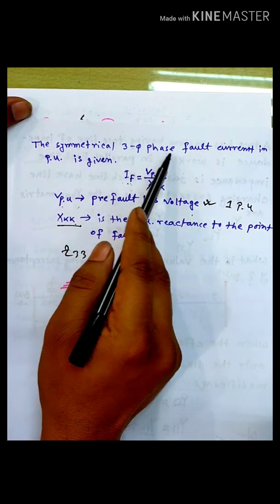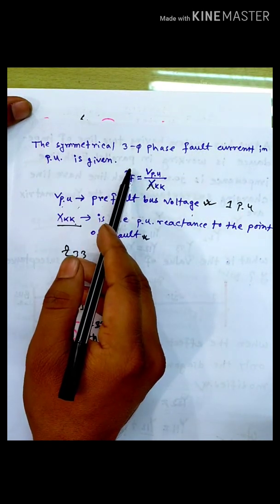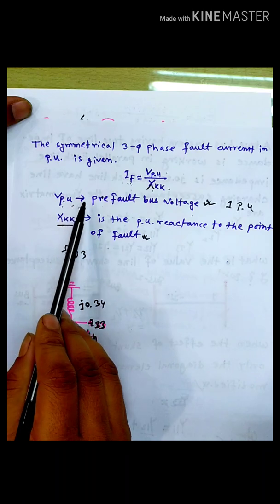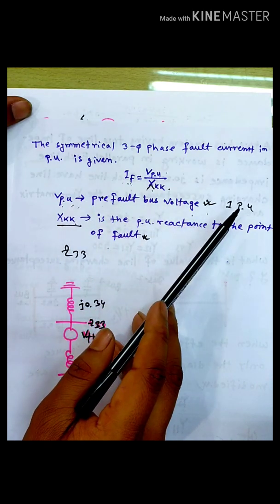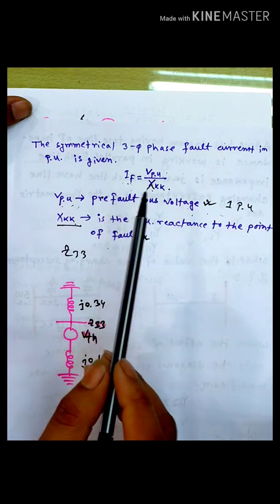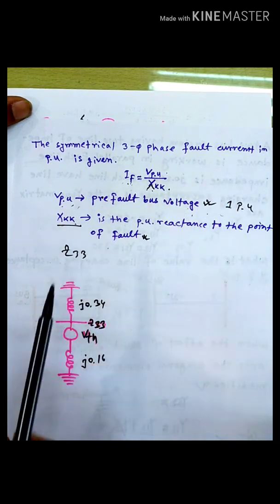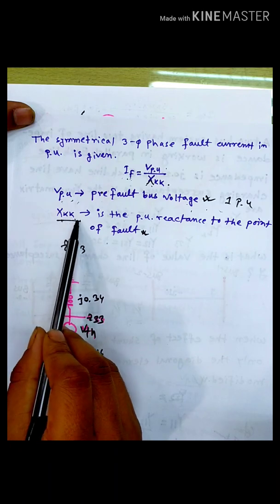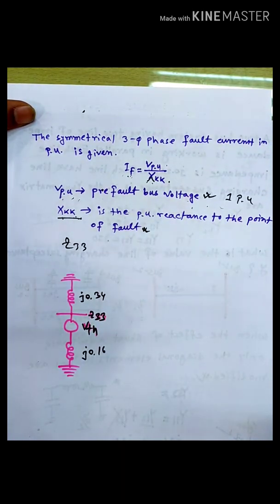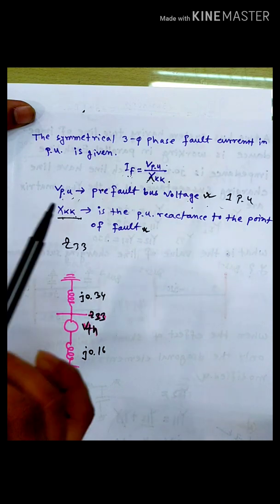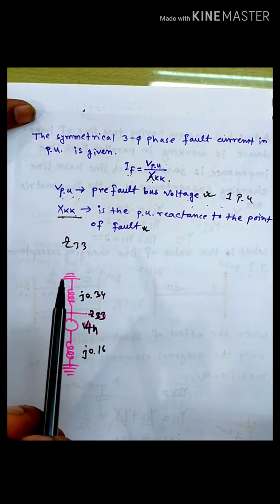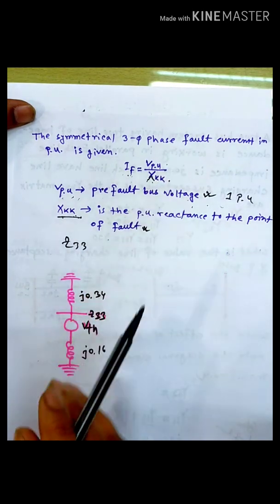The symmetrical 3-phase fault current in per unit is given by V per unit divided by x. This is the pre-fault voltage in per unit. If you don't have the pre-fault voltage in per unit, then you assume 1 per unit. The x_kk is the per-unit reactance to the point of fault. The total equivalent reactance to the point of fault — x_kk is the total equivalent.